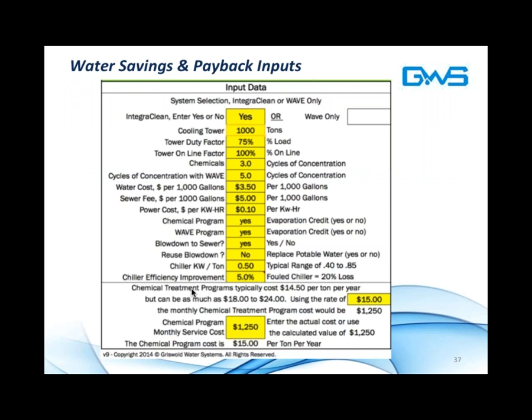Let's talk briefly about water savings and payback on the financial side before we wrap this up and take a few questions here. This input data shows a cooling tower that was demonstrated earlier in our example of 1,000 tons running at 75% load year-round, say for a data center. Chemicals operating at 3 cycles of concentration can be converted to, with wave, approximately 5 cycles of concentration, which is to say we can concentrate the minerals greater.